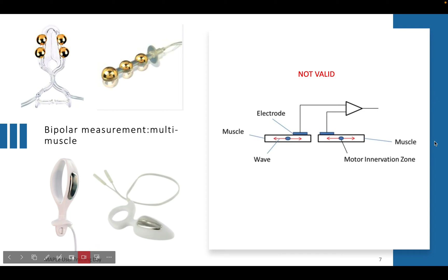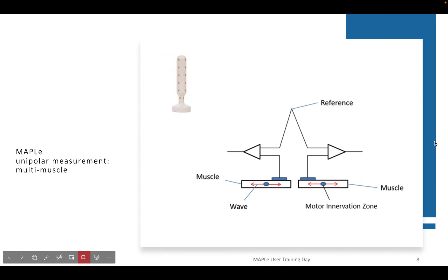If you are using a device that is using a bipolar measurement function, and those electrodes are spanning more than one muscle, they are then feeding back a summary of information across multiple muscles. So we lose the specificity and we get an average for the muscle group, which is useful in some circumstances, but when we're dealing with asymmetries, for example, after a forceps delivery with episiotomy, we may have an asymmetry between the right and the left pelvic floor, and we would not be able to see in detail what's going on from one side to the other, and we also wouldn't be able to treat one side more so than the other with a bipolar measurement function. However, with Maple, we would be able to do that. So with the unipolar measurement, we get the specific information from each muscle, and we can also treat each muscle specifically.